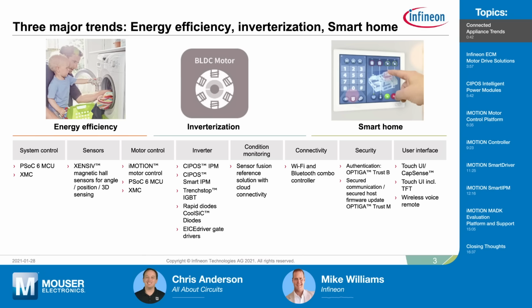Also, inverterization, which introduces variable speed motor control and the utilization of permanent magnets or BLDC motors, allows for significantly improved efficiency of the motor. And this really comes down to a shift from the PSC or permanent split capacitor motor to an ECM motor, where you're going from around 60% efficiency to greater than 80% efficiency.